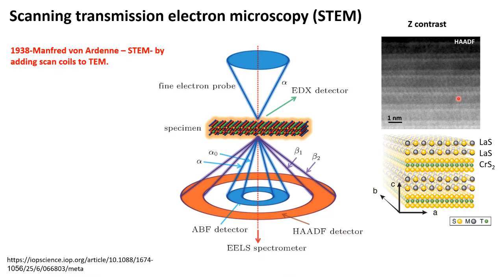All right. So this slide is meant for the young operators, and also, of course, users. When you are doing your samples, the very important first thing is that you need to know what kind of information you are planning to achieve from your sample. For example, if your interest is in biological samples, where contrast is more important than resolution, we can opt for low kV TEMs, and then you can play a little bit with your condenser apertures and spot size.